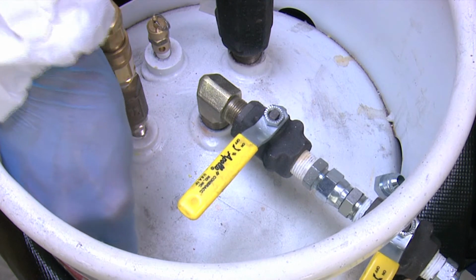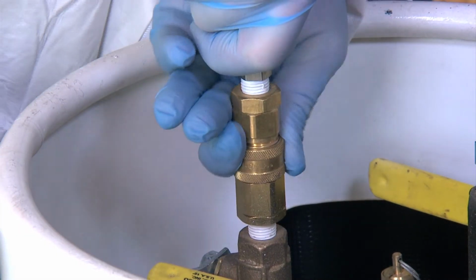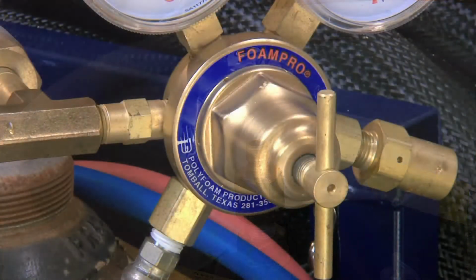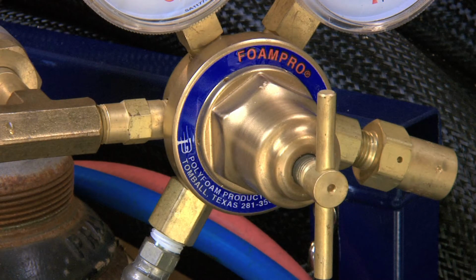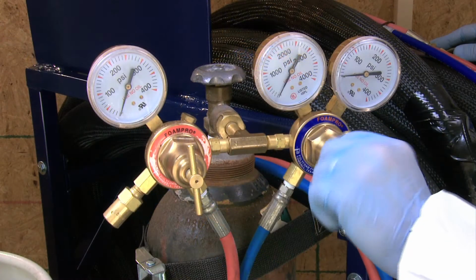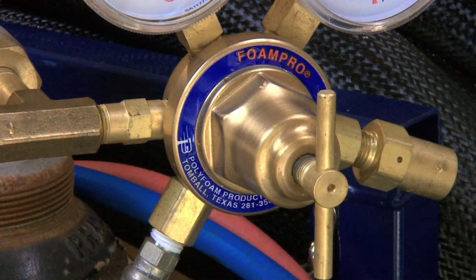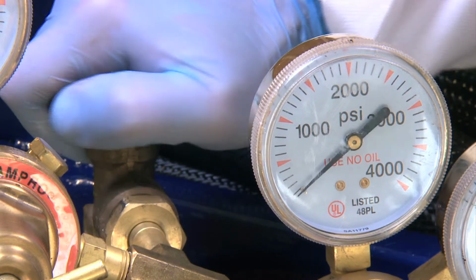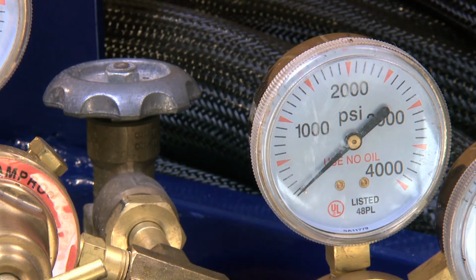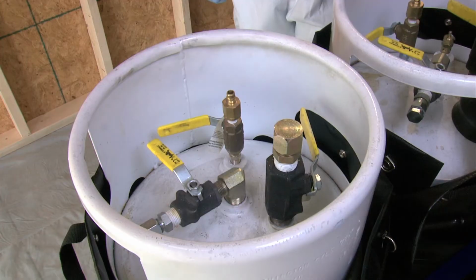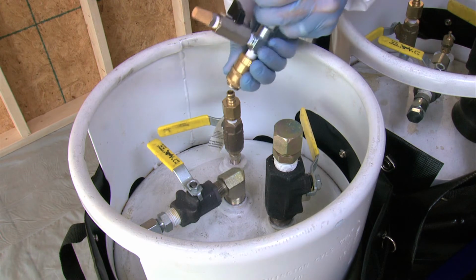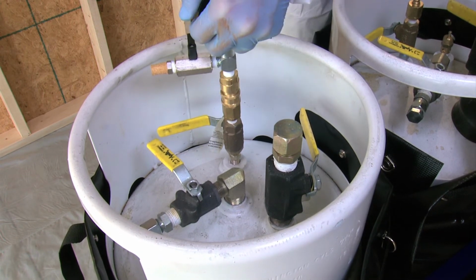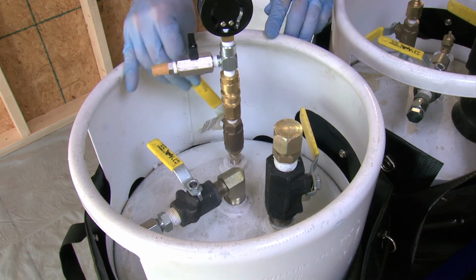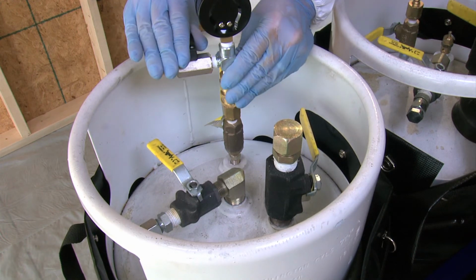Close the nitrogen valve on the chemical cylinder. Remove the nitrogen hose from the cylinder. For the chemical cylinder being adjusted, turn the regulator adjustment valve counterclockwise 1 full turn. Make sure the pressure release valve is closed. Attach the pressure release valve to the chemical cylinder by placing it on the nitrogen fitting on the chemical cylinder. Open the nitrogen valve on the cylinder and verify the cylinder pressure.